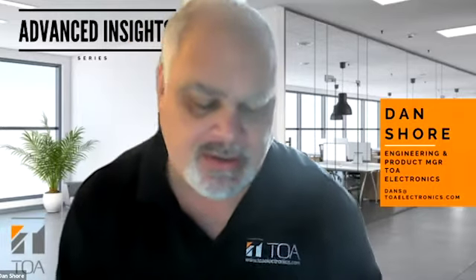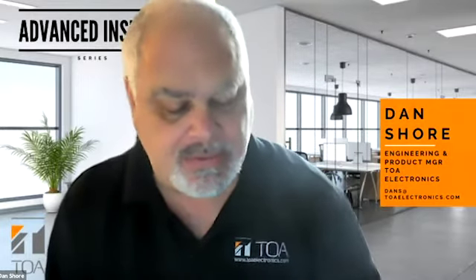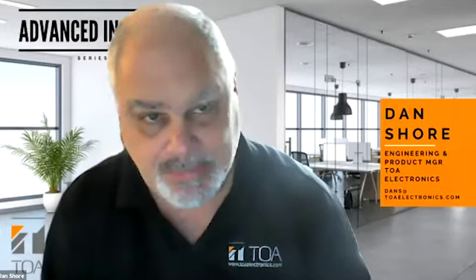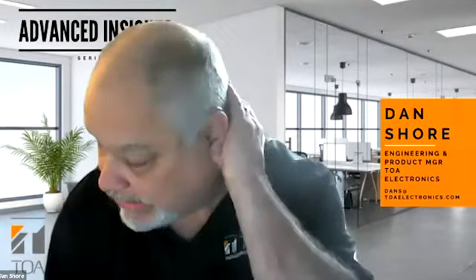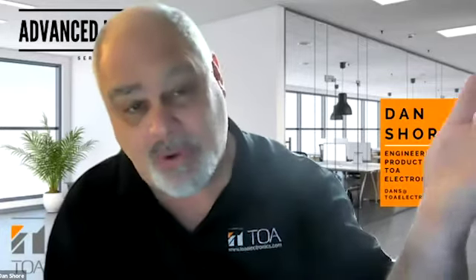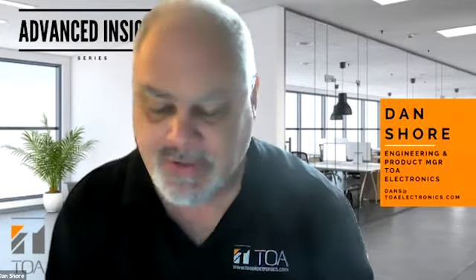Typically, if it's going to be used for UL2572, which is going to be mass notification, what we call voice alarm, not fire alarm, the AHJ will be flexible about the speakers and you can drop the head end in. That's not the case on fire generally. You're going to do fire alarm, UL864 listed, and have fire voice with our system, that's going to need to use speakers that are rated for life safety. Now, TOA has life safety speakers. We have a wide range of them. Ian mentioned that a little bit earlier. So paging horns, box speakers, pendant speakers, regular ceiling speakers, high quality RF-122 is listed for life safety. So you have options there, but if it's gonna be fire alarm, it's not gonna drop in.